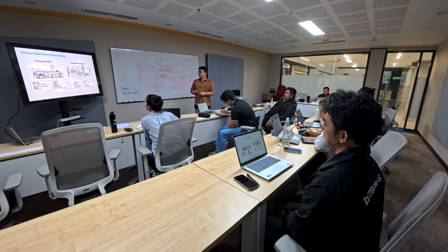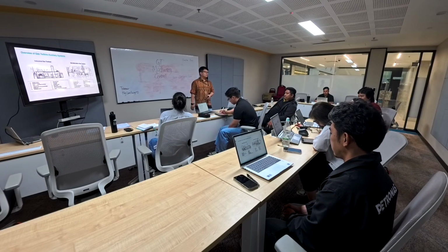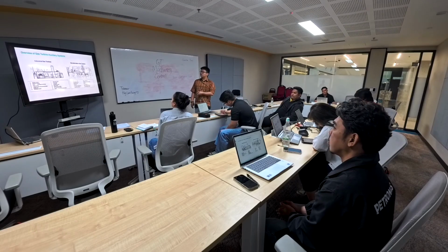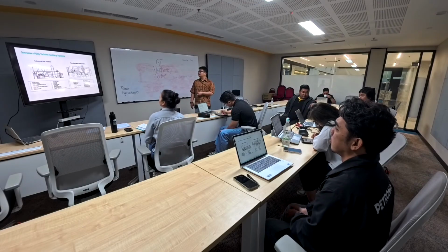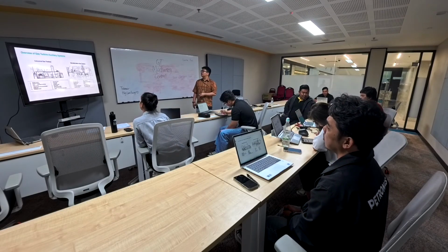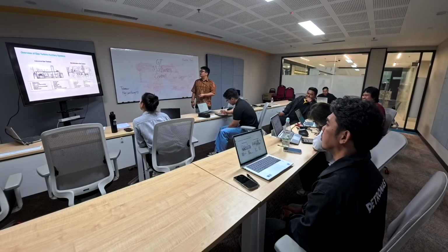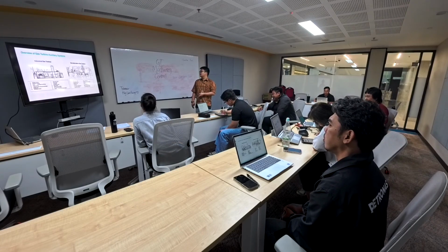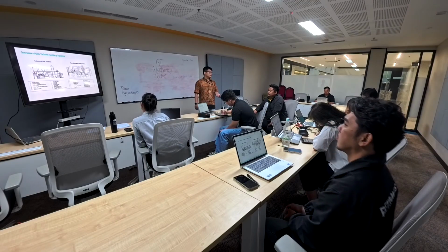Generally, if I were to summarize, you will always have your lube oil system, your fuel system, your air system, and your starting system. These 4 normally are the ones that give you problems. If you cover these 4 systems, most probably you have already covered 80% of the problems. There are also some other auxiliaries, for example your ventilation, your enclosure, your control system, your base plate, your coupling, firefighting system, and water washing system as well.